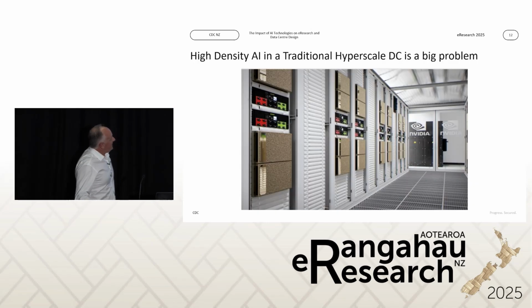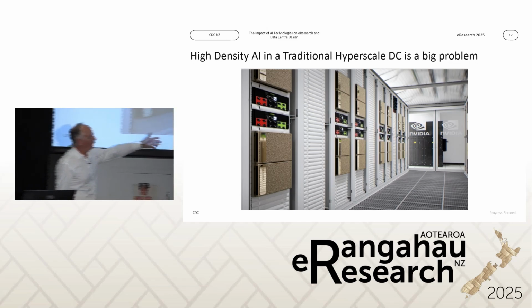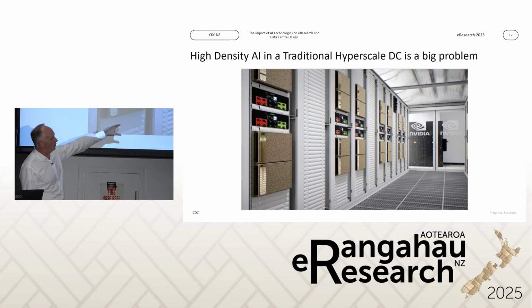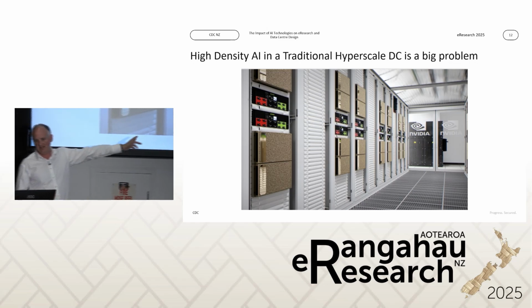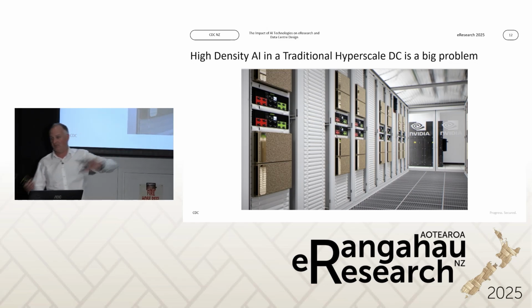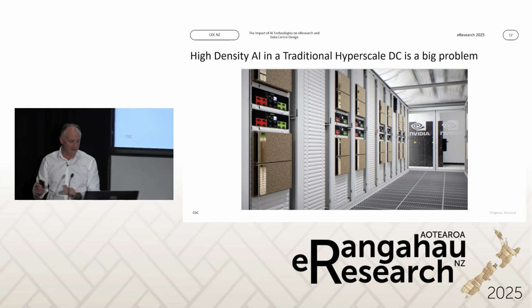In terms of what does it mean for data centers globally, it's a pretty big problem. This is actually 2-generation-old GPUs installed in a traditional data center with a raised floor, and you can see the heaps of space blanked out, massive grills in the floor already, containment, and that's only doing 18 kilowatts a rack, not 120 or beyond.